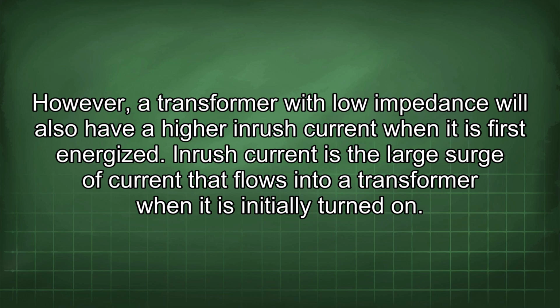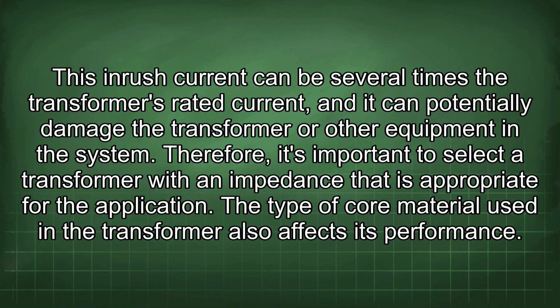However, a transformer with low impedance will also have a higher inrush current when it is first energized. Inrush current is the large surge of current that flows into a transformer when it is initially turned on. This inrush current can be several times the transformer's rated current, and it can potentially damage the transformer or other equipment in the system. Therefore, it's important to select a transformer with an impedance that is appropriate for the application.